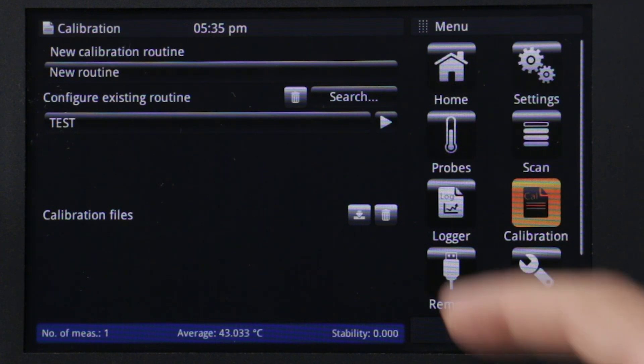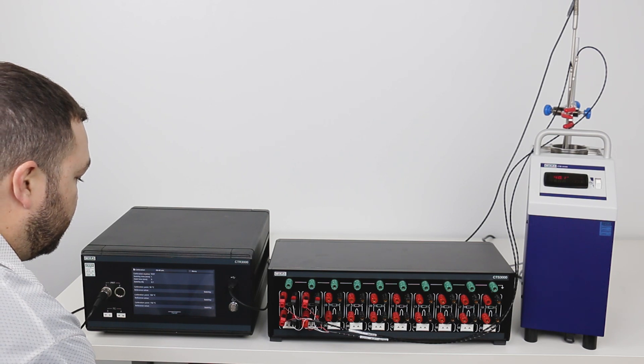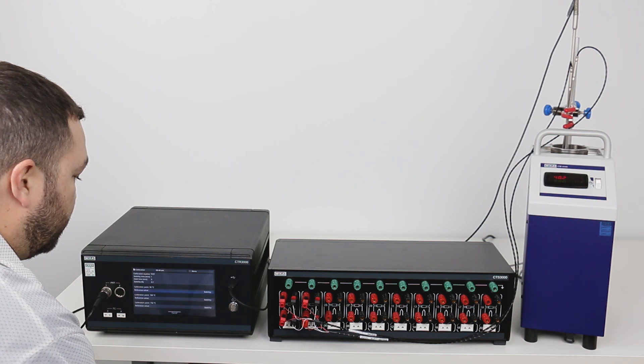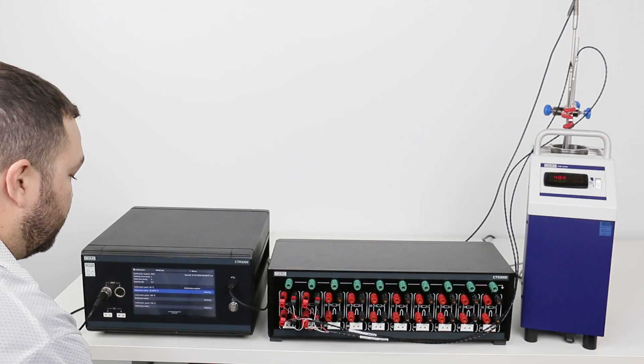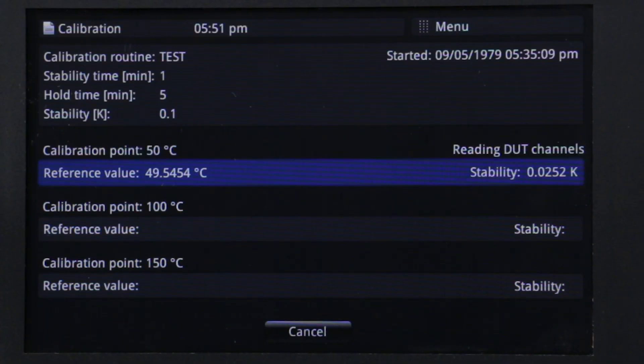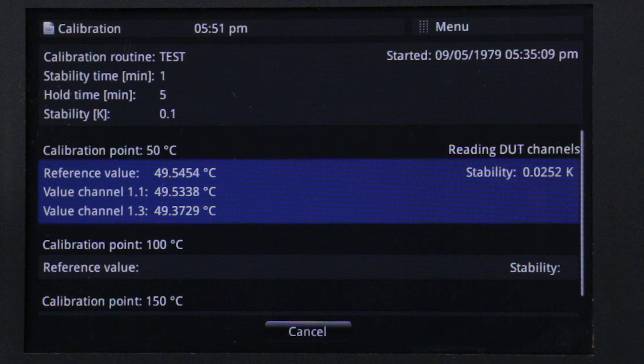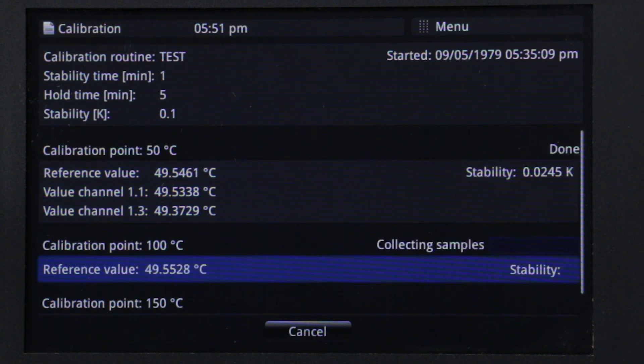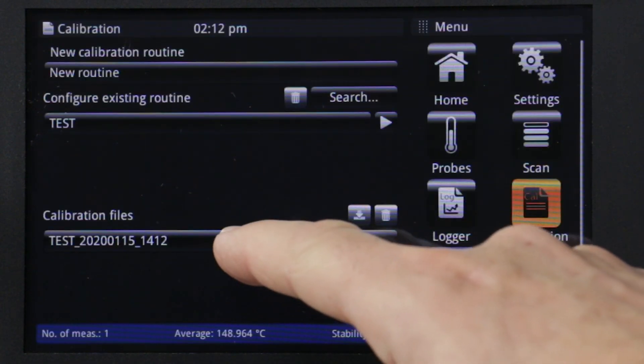After all parameters are entered, touch the play button next to the routine name to begin the calibration. The CTR3000 commands the CTB9100 to a prescribed sequence of temperature set points. After the stability parameter is satisfied during the stability time and the hold time has passed, the CTR3000 then records readings from the reference probe and all test probes. When the calibration sequence is complete, data can be downloaded for reporting.